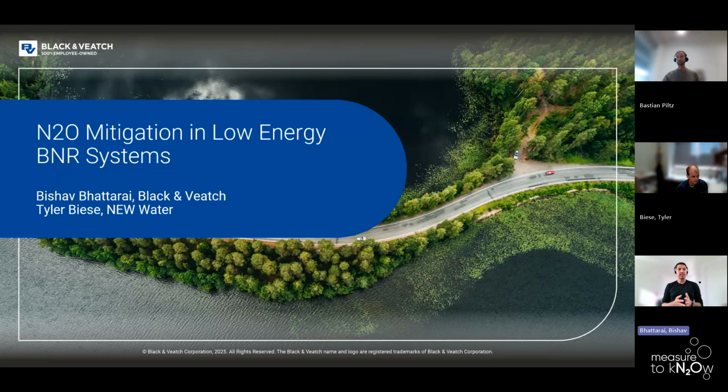But again, that might be due to our process not being optimized. We might have a short anoxic time, and we don't have the flexibility to change the cycles with the current system we have. But it was higher, like 3 or 4 percent in terms of the emission factors. And with the synthetic formate, it was way lower than 1.